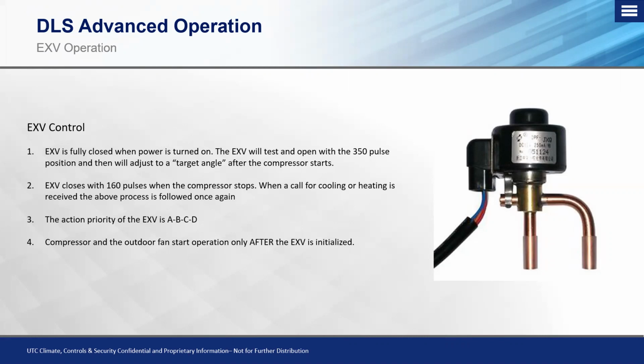Okay, so when that EXV goes to that test function, it'll open up to the 350 pulse position, which is fully open. And then it will adjust after the compressor starts to a target angle. And again, that's going to be based off of that T2B sensor, which is on the outlet of that EXV. Essentially it's just telling it where the EXV needs to be to feed the proper amount of refrigerant to the indoor unit, depending on whether we're in heat or whether we're in cool. The EXV closes with 160 pulses when the compressor stops.